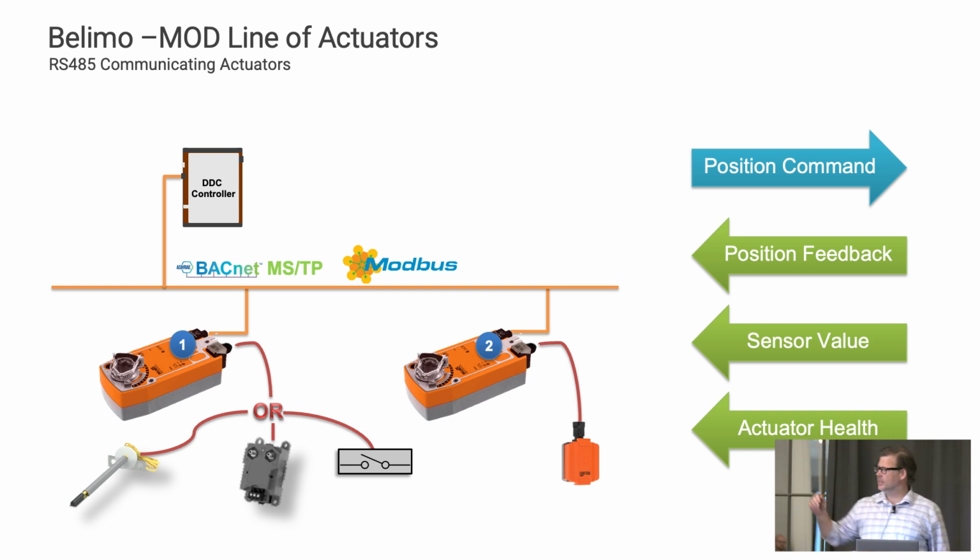Okay. All right, so we call it feedback for free because you're already connecting to it, you get all this information from this device. So if a damper gets stuck, someone clutches it out and forgets to release it, this is some of that information that could be really useful when troubleshooting, like zones over temp, feedback and set point aren't matching. These are just little pieces of information that you get by connecting these devices.